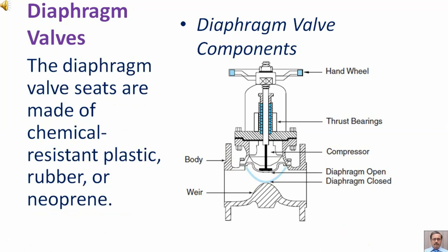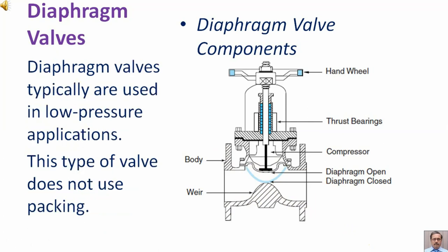Diaphragm valve seats are made of chemical-resistant plastic, rubber, or neoprene. Diaphragm valves are typically used in low-pressure applications. This type of valve does not use packing.